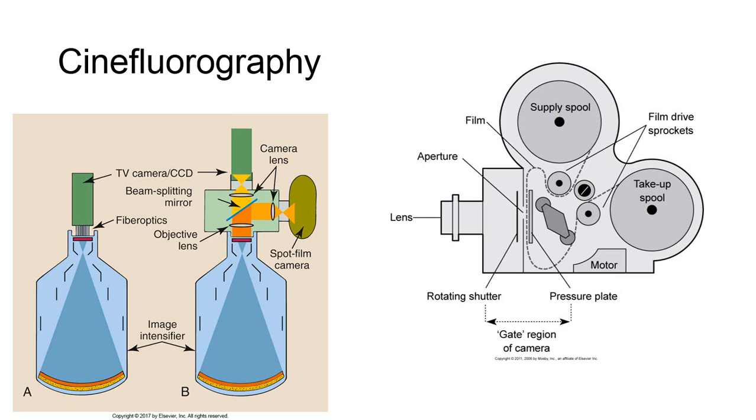Using this method, a cinegraphic recording of the fluoroscopic image occurs at the same time you're able to view the live fluoro image on the TV monitor. Its major applications have been primarily in cardiac cath lab and interventional radiography, for which 16mm or 35mm film is typically used, though 70mm film is also available.